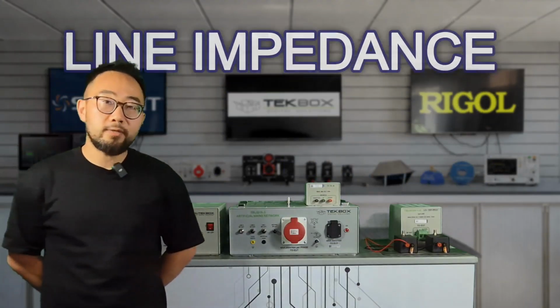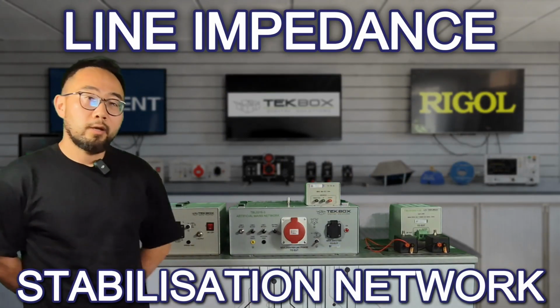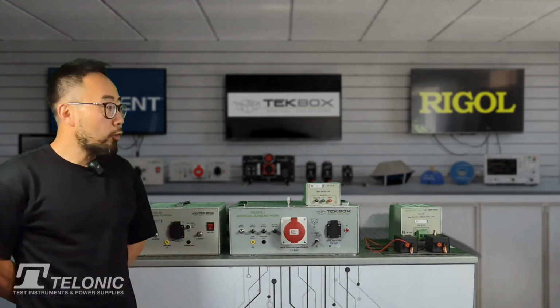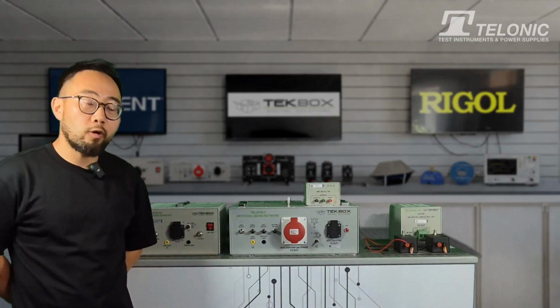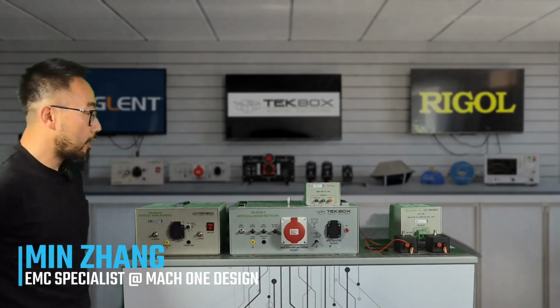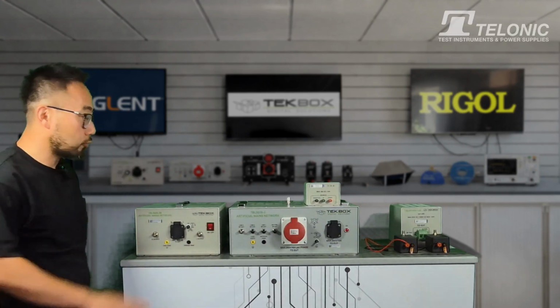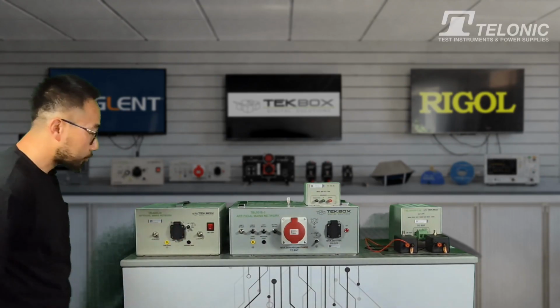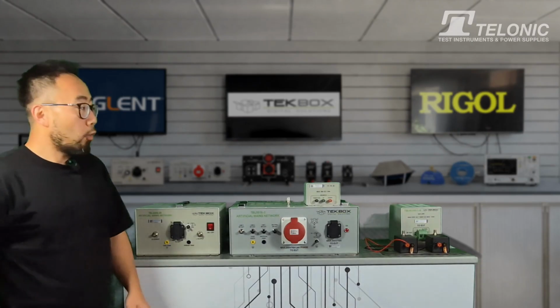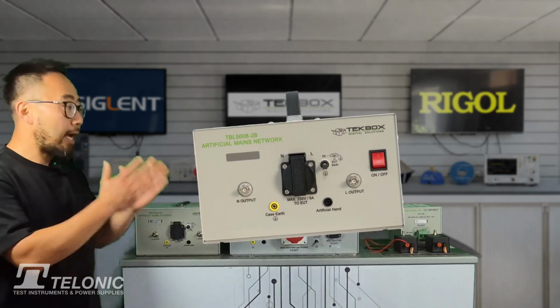LISN stands for Line Impedance Stabilizing Network. They are the devices for measuring conducted emissions. Today we're going through different types of LISN and have a quick general overview. My name is Min, I'm an EMC specialist, and today I'm here at Telonic and we're going through different types of LISN review. Typically speaking, we can divide LISNs into two types, AC types of LISN and DC types of LISN.